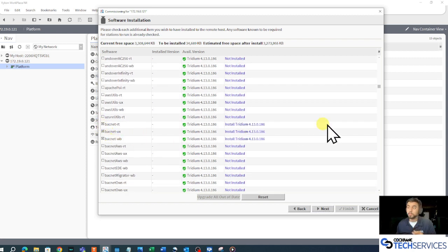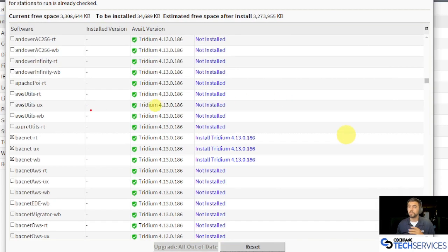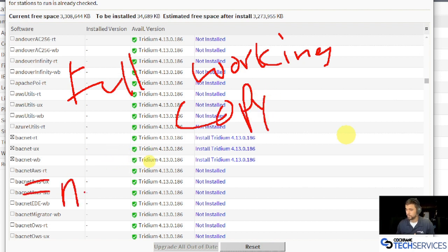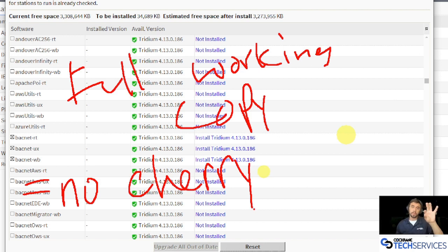I advise that we build this station offline or have a working, fully functional station copy. If we have a fully functional station copy, full working copy means no cherry picking. By cherry picking, I mean specifically and explicitly choosing what modules to send over to our commissioning JACE.